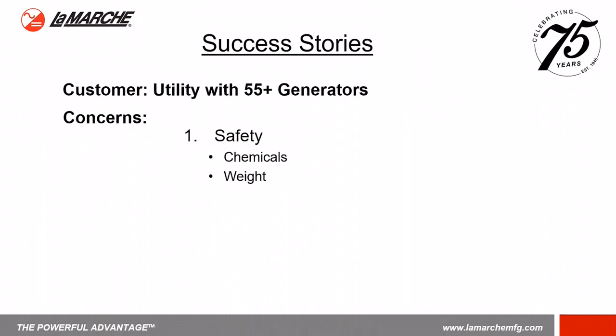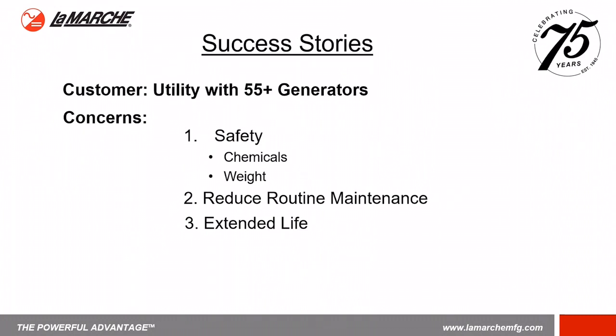The weight. What they wanted to do is instead of call their local dealer that does the servicing on the generators, they wanted their own technicians to go and do servicing on the generators. And lifting 80 or 100-pound batteries was a big concern. They wanted to reduce the routine maintenance. Now that their own technicians were doing it, they wanted to make sure the batteries they select are long-term and do not require as much maintenance as lead acid might. They wanted to make sure the batteries have an extended life versus a typical lead acid or NiCad battery system. And the final reason was minimize cost impact. One would switch over and also routine maintenance.